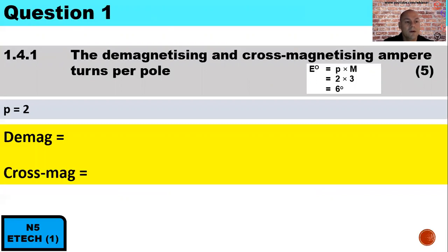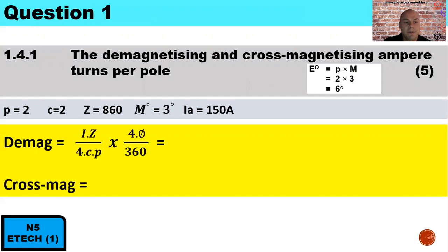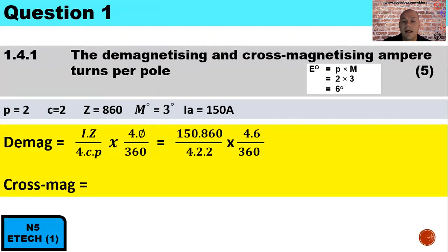This is a four-pole machine, therefore two pole pairs. It is wave wound, therefore C equals 2. Z, the total number of armature conductors, is 860. The mechanical degrees is 3 and the armature current is 150 amps. To determine the demagnetizing ampere turns per pole, we use: current multiplied by Z, over 4 × C × P, multiplied by 4 × theta over 360. That is 150 × 860 ÷ (4 × 2 × 2), multiplied by (4 × 6 ÷ 360). Therefore, the demagnetizing ampere turns per pole is 537.5.